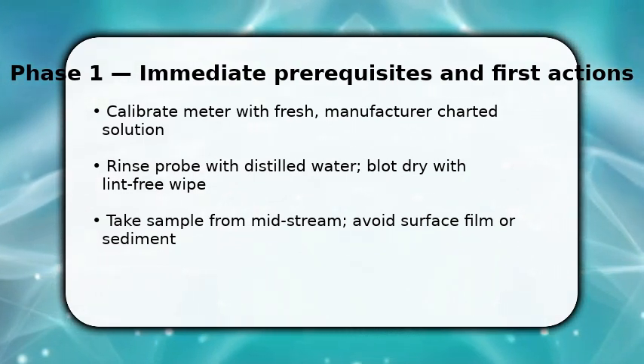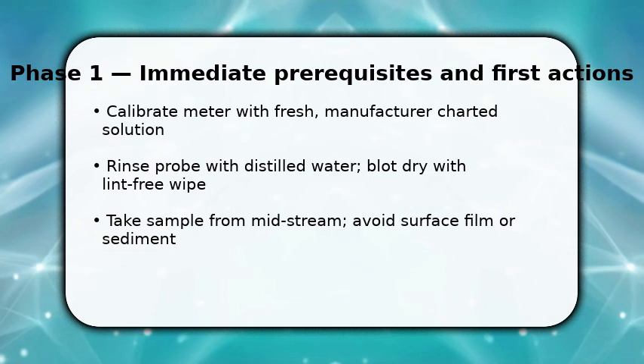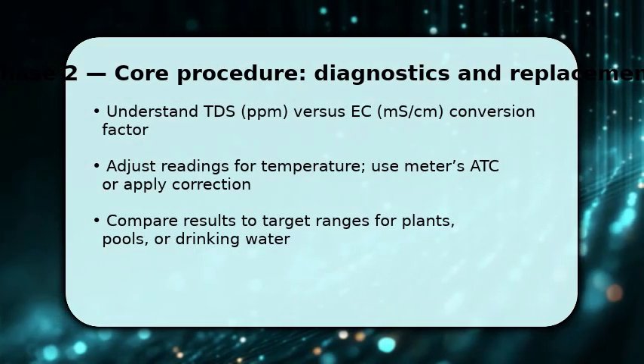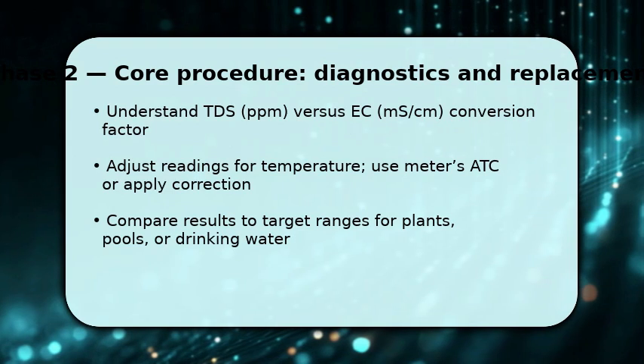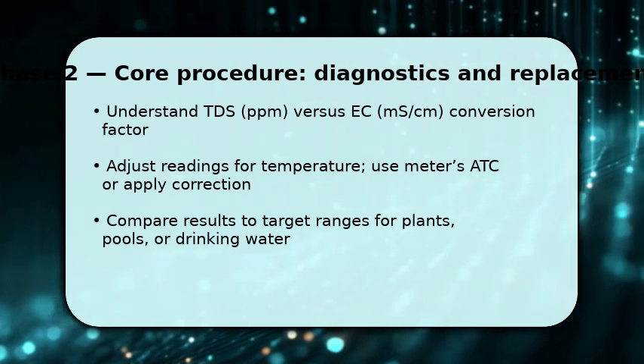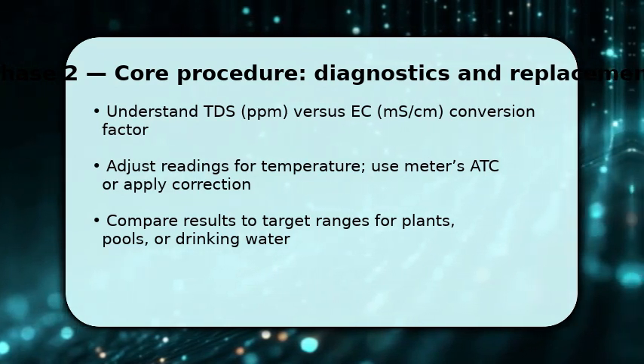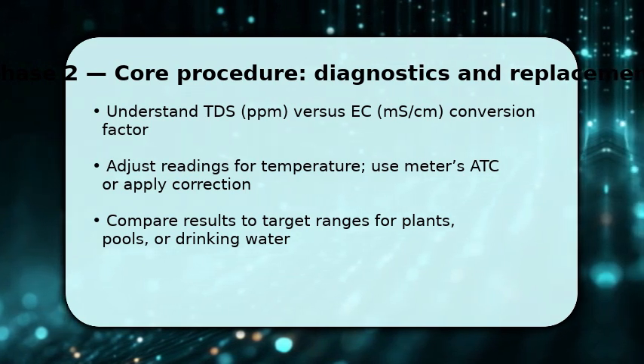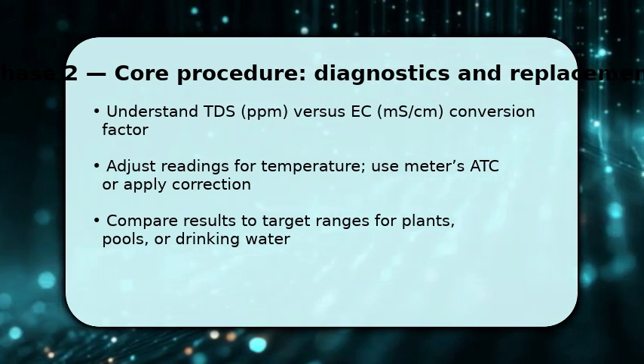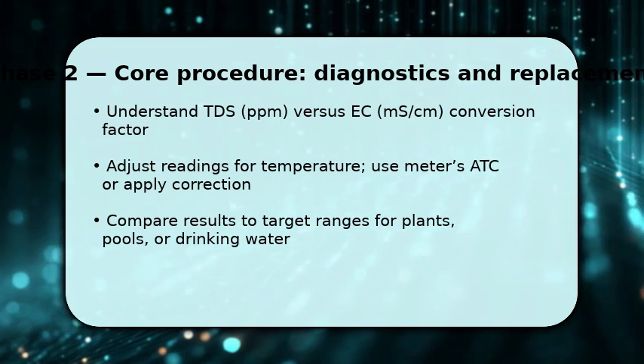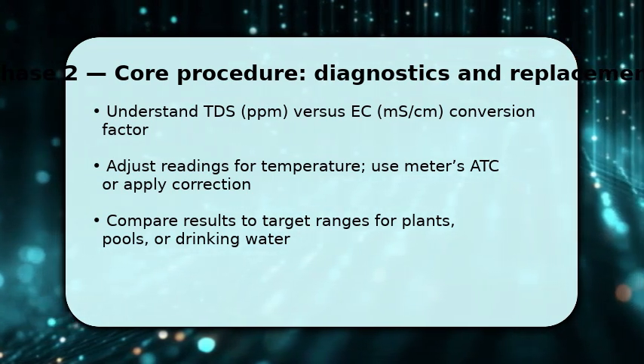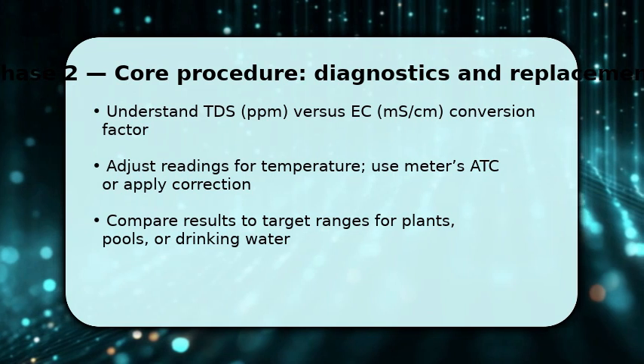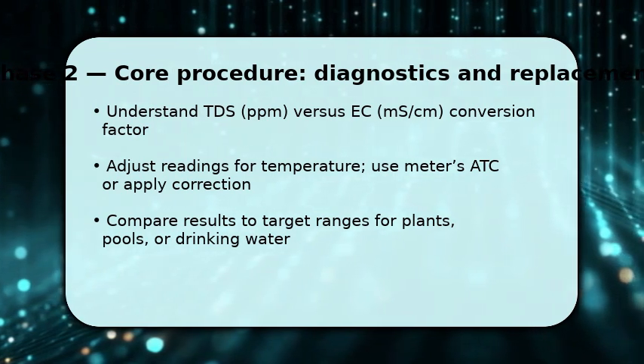EC gives conductivity in mS/cm while TDS displays ppm, a conversion factor often 0.5 or 0.7 converts EC to TDS. If your meter lacks ATC, manually correct for temperature. Most corrections are per 1 degree C from 25 degrees C. Once done, compare values to target ranges for hydroponics, pools, or potable water.